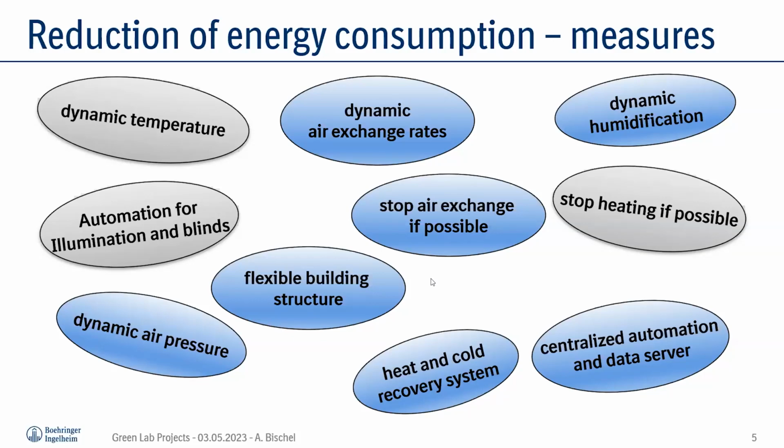We made a calculation about the saving potential, and we saw that on the site of Biberach, we could save around 1.5 to 2 million euros per year, only by reducing the humidification in wintertime. We reduced it by setting the level to 0% at night, on Saturdays and Sundays, during off-work time. And in working time, we reduced the level from 50% to around 40% humidification rate.